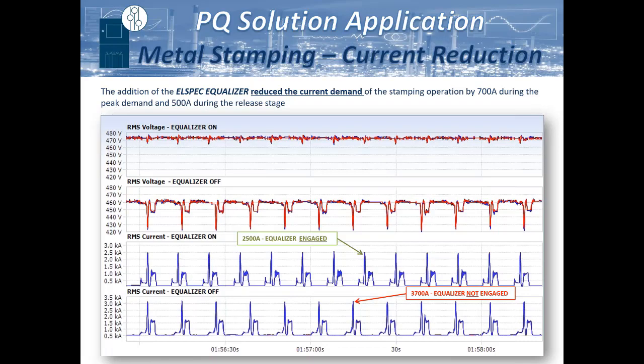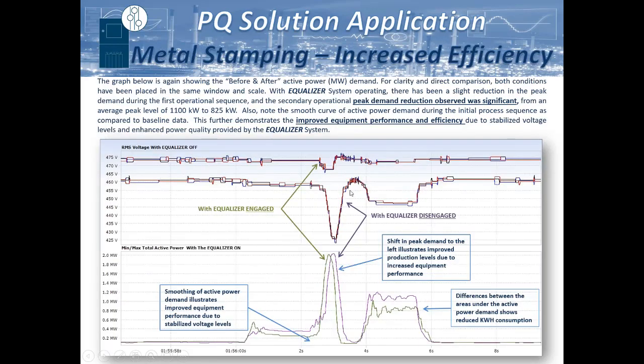And this is probably one of my favorite charts here, because we can superimpose the before and after on top of each other. So you can see the average nominal level rising. And in the baseline measurements, the active power in the purple, before the system engaged, you can see this very jagged aspect to the active power. And this jagged profile is a response to the voltage drop. As the voltage drops, each motor is going to have a different torque to kilowatt ratio. So when that voltage drops, it's constantly chasing that voltage, trying to get it to respond in the way that it needs to for the process.